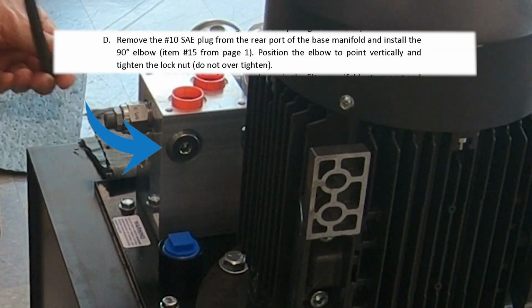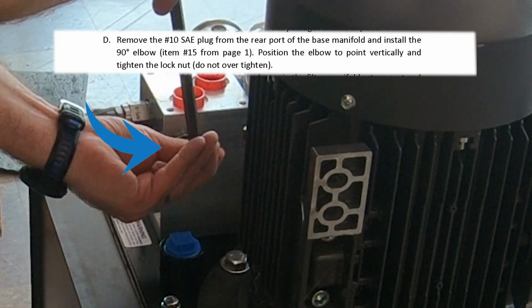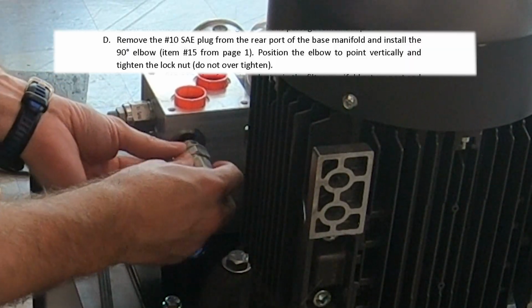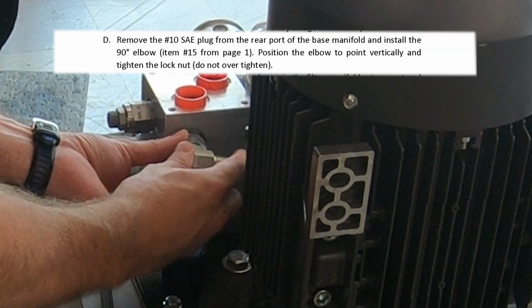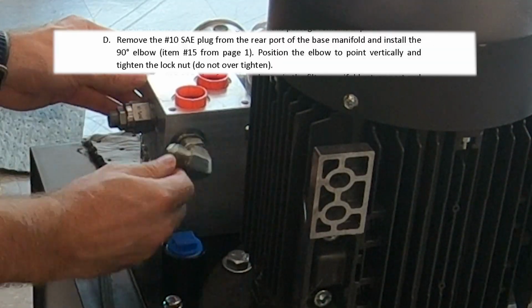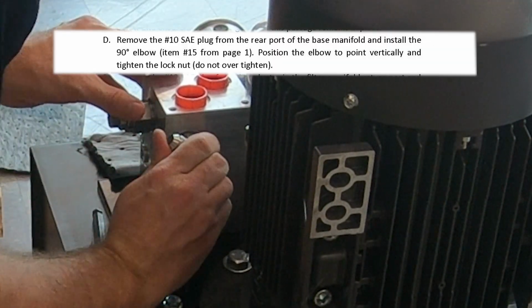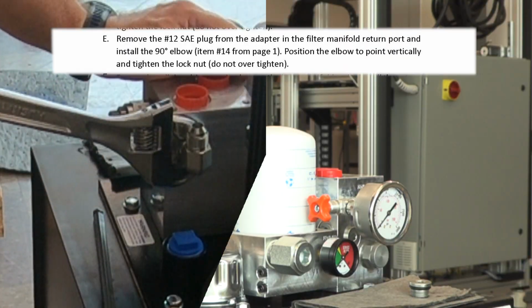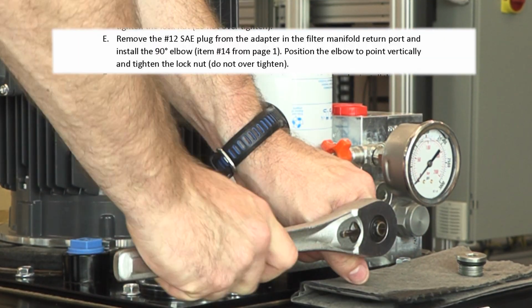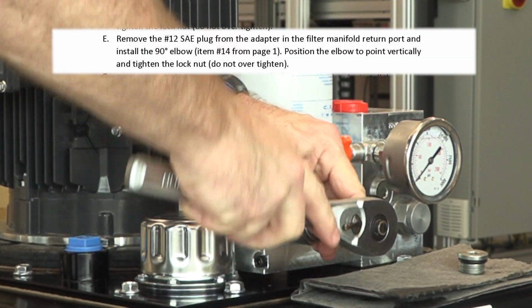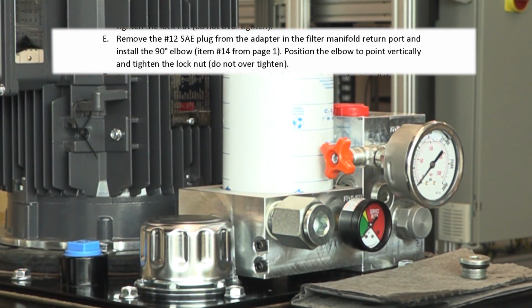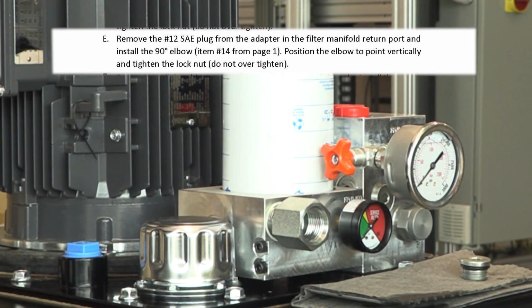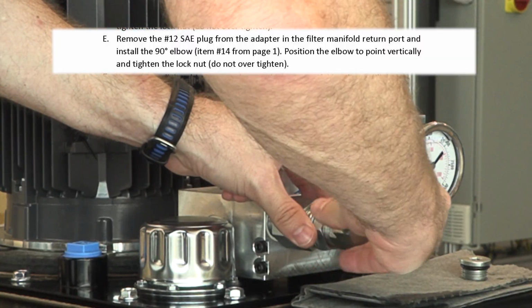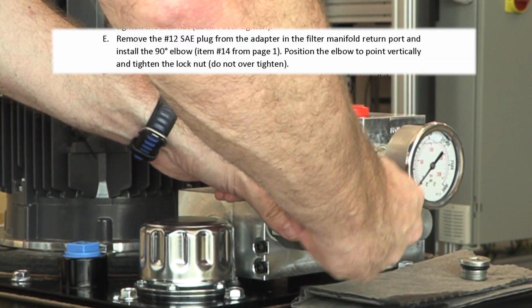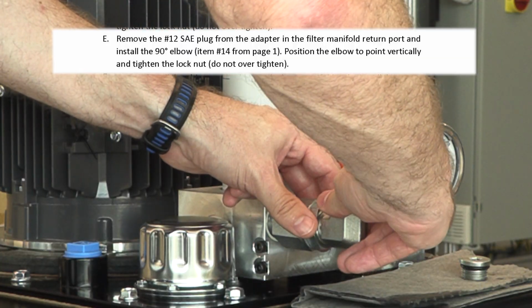Next, remove this number 10 SAE plug from the rear port of the base manifold and install this included 90-degree elbow. Position the elbow to point up and tighten the lock nut. Remove the number 12 SAE plug from the adapter in the filter manifold return port and install the other included 90-degree elbow and position the elbow pointing up as well and tighten the lock nut.